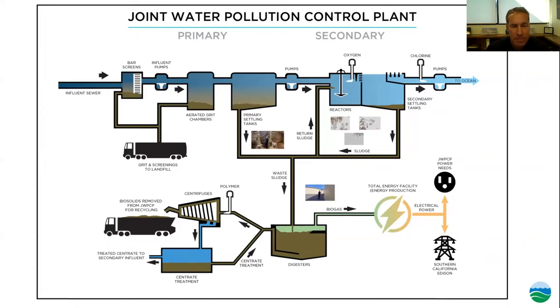Question: there was an orange color at the bottom of some of the tanks in the videos — was that rust or something else? The orange is actually from iron. For odor control, we add ferrous chloride — which is iron — to the sewers. The sewage goes anaerobic in the collection system, and the ferrous chloride combines with the hydrogen sulfide to neutralize that odor and keep odors down in the collection system. So that little rusty color is from the iron we add for upstream odor control.